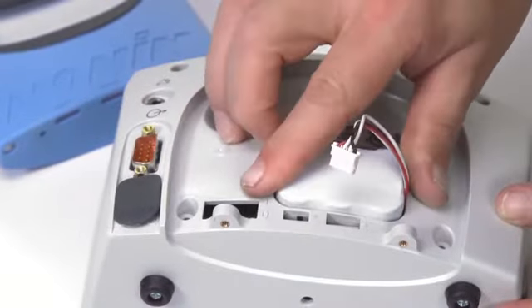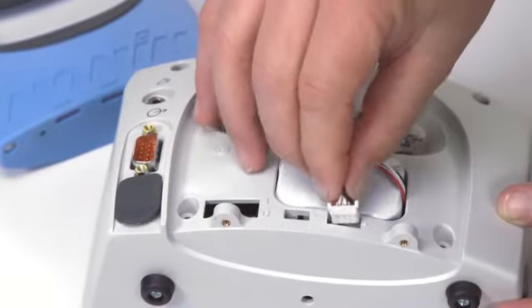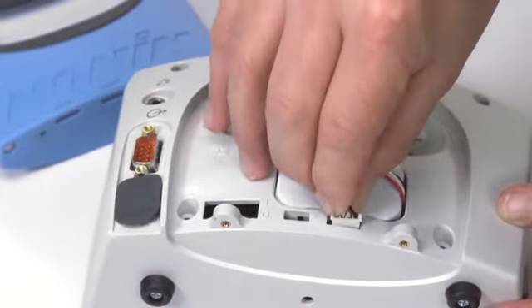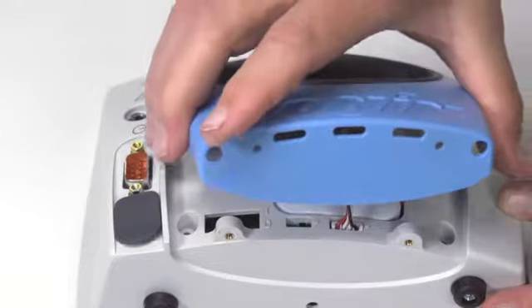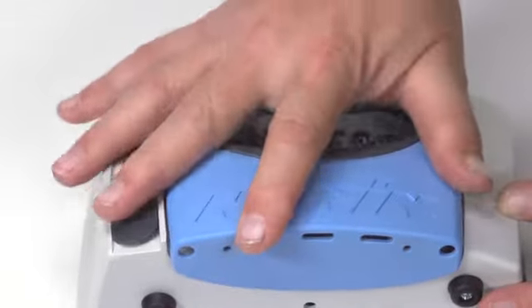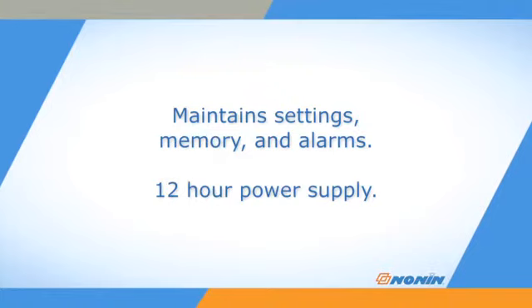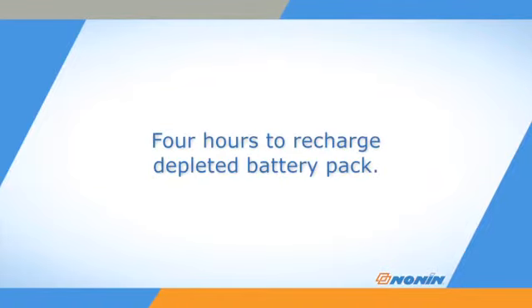It must have the rechargeable battery pack from Nonin Medical installed in the Avant 9600 oximeter to operate, even when using AC power. This battery pack maintains settings, memory, and alarms when the oximeter is unplugged, and may also act as the primary power supply for up to 12 hours. Recharging takes about 4 hours when the battery pack has been completely depleted.